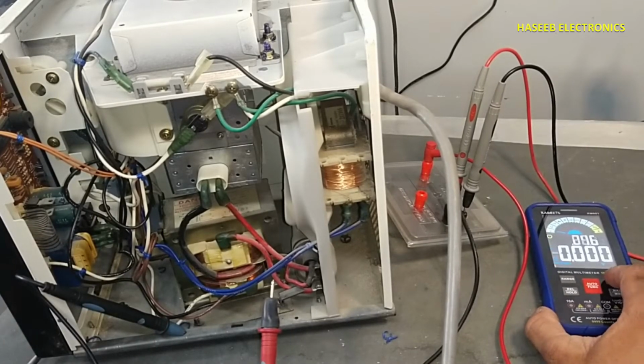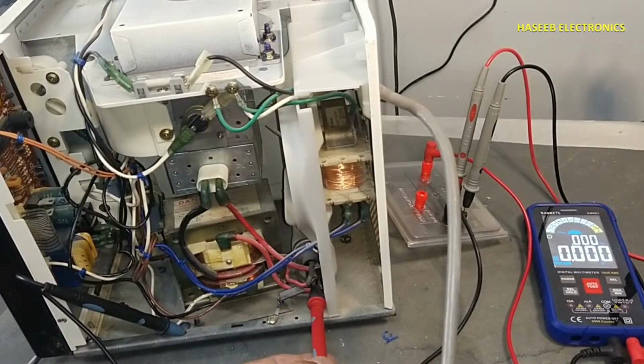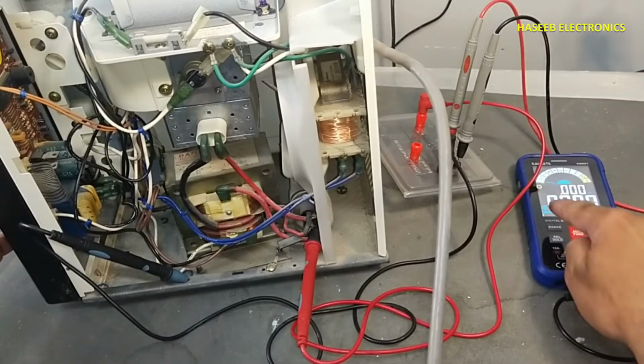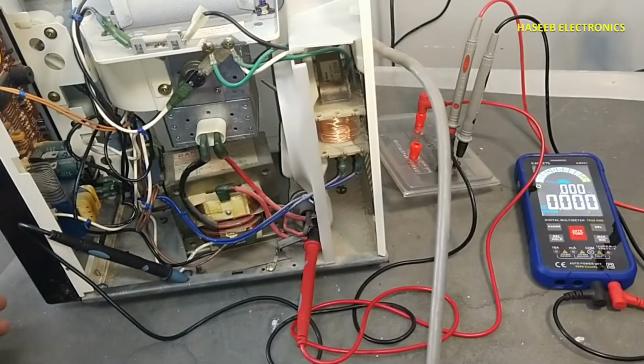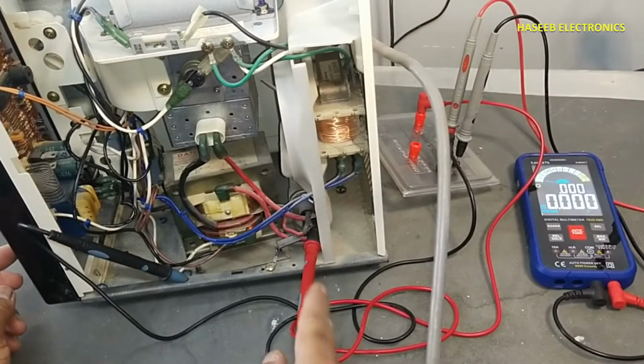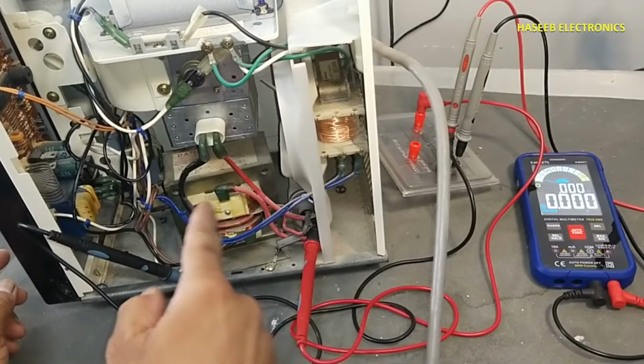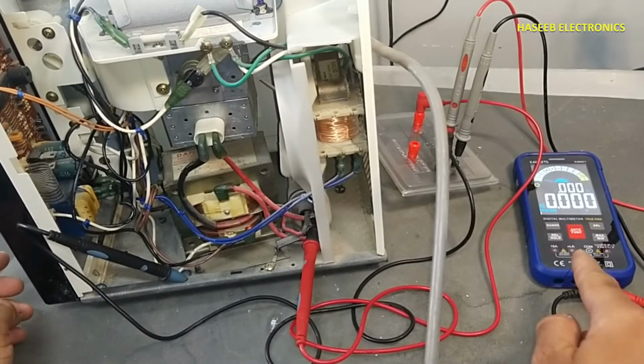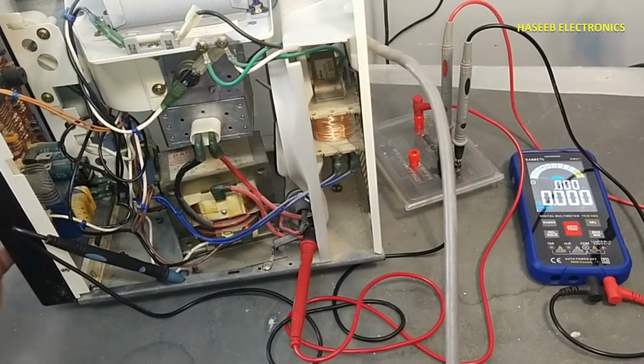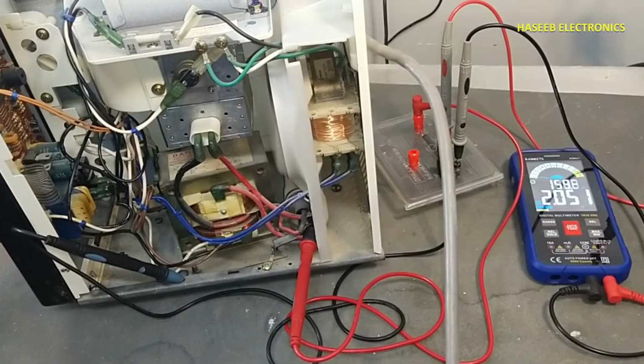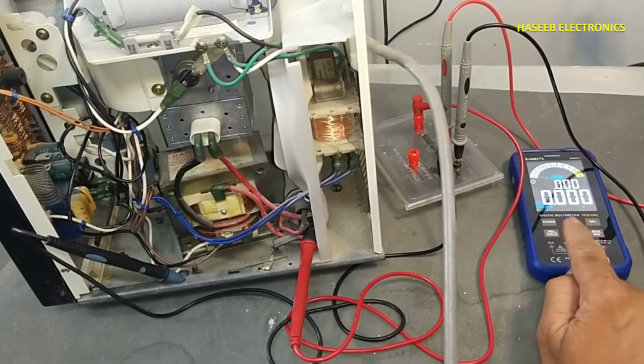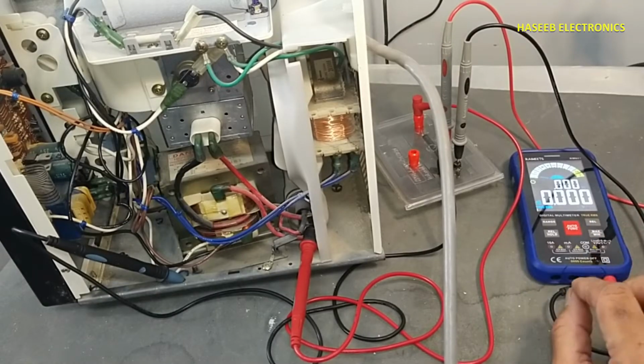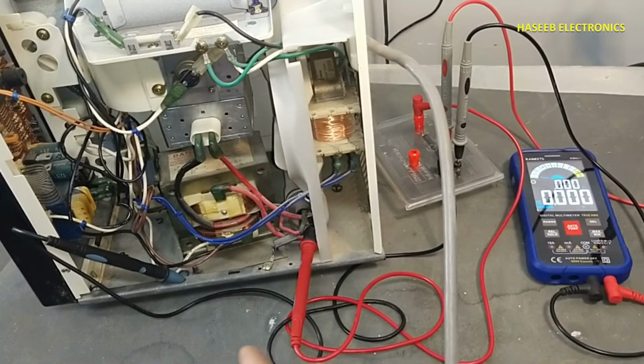First we will measure the AC voltage, that is the output of this high voltage transformer. I connected one wire to the chassis and one wire to the AC output terminal of the high voltage section. Now I will provide a 1 minute cooking profile and we will check the voltage. It is 2.051. Now we see 2.05. That means 2050 volt AC is coming out from this transformer.